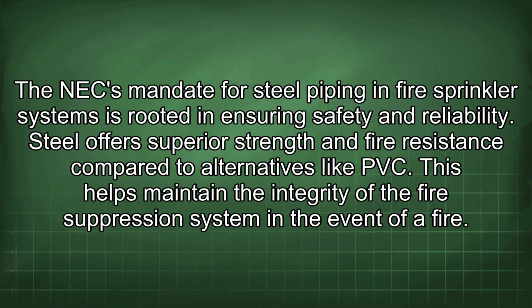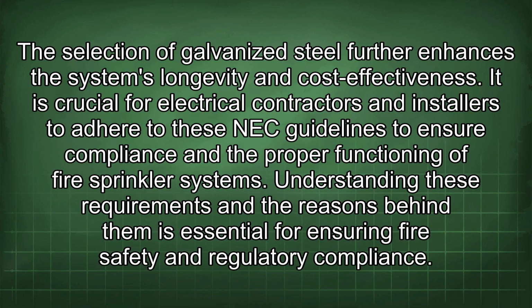The NEC mandate for steel piping in fire sprinkler systems is rooted in ensuring safety and reliability. Steel offers superior strength and fire resistance compared to alternatives like PVC. This helps maintain the integrity of the fire suppression system in the event of a fire. The selection of galvanized steel further enhances the system's longevity and cost-effectiveness. It is crucial for electrical contractors and installers to adhere to these NEC guidelines to ensure compliance and the proper functioning of fire sprinkler systems.